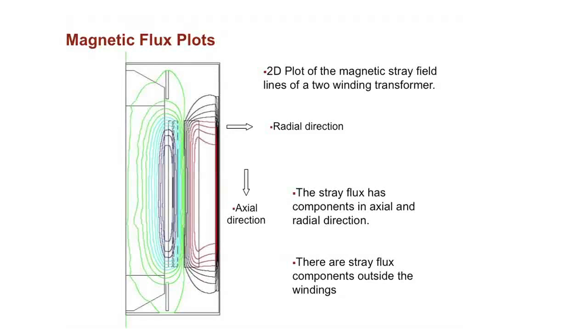When you have a short circuit event, you have all this extra flux, and what it wants to do is drive the windings out, the inner one in and the outer one out, and then it wants to have it grow actually. And so it actually matters. It makes a big difference which winding you're looking at, which kind of forces it has to sustain. But you can just imagine the clamping of the windings, how the windings are made, is very important.